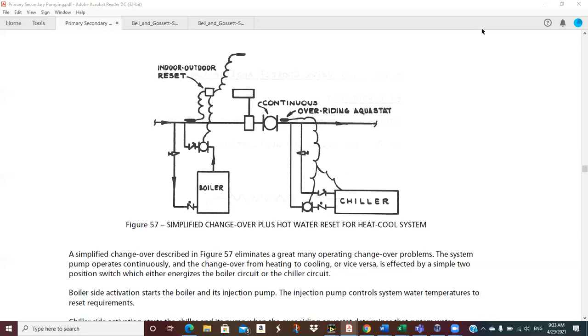So you've got to have some sort of controls on this thing that will, let's say you've been on heating, you turn the boiler off or you stop that circulating pump, but you have to continue to circulate that water through the loop, because the only way you really have to cool it down is to put it through the coils in the space and put that heat into the building. Now, you would hope that you time this appropriately so that those people want that heat and that you don't warm them up and make them comfy, and then you overheat them to cool the loop down. And then you get the water cool enough, say 75, 80, that you could start bleeding it through the chiller. And then the chiller has to cool the loop down before you can start doing air conditioning. And you just have a big control mess. And so that's kind of what these systems have to accomplish if you have a two-pipe system.